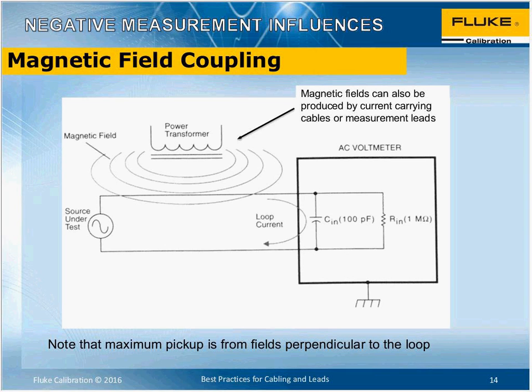So that's why you use coaxial cables, where the conductors run coaxially, one inside the other. That gives you a good electrostatic shield, and it also gives you a good magnetic shield. Neat twisted pairs, where the wires are twisted very closely together to minimize that loop area, will be a benefit as well. And if you can arrange that your leads are at right angles to the magnetic field, that's even better still, because the magnetic field has to cut through the loop in a perpendicular direction. So if you can orient the leads so you minimize the crossing of the magnetic field.